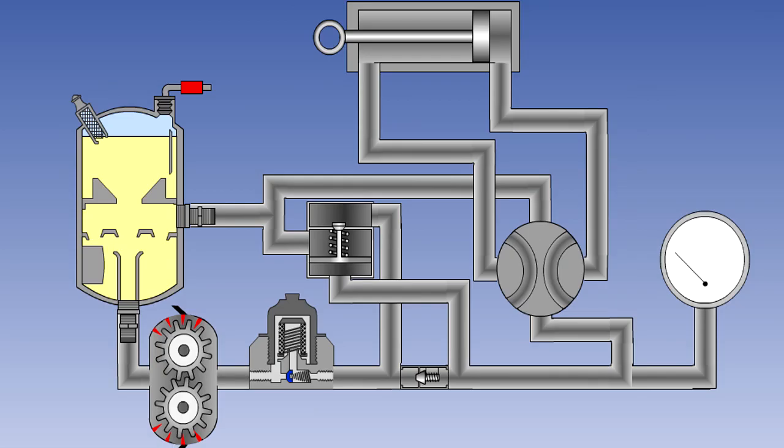With the system not operating and the pressure is zero, the ACOV will be in the cut-in position. When the pump starts operating, pressure will build up until normal system operating pressure is reached. The pressure on the bottom of the piston will overcome the spring. The piston will move up, opening the poppet valve and allowing the pump to return its fluid output to the reservoir without any load. There will still be fluid flowing through the pump to cool and lubricate it. This is the cut-out position.